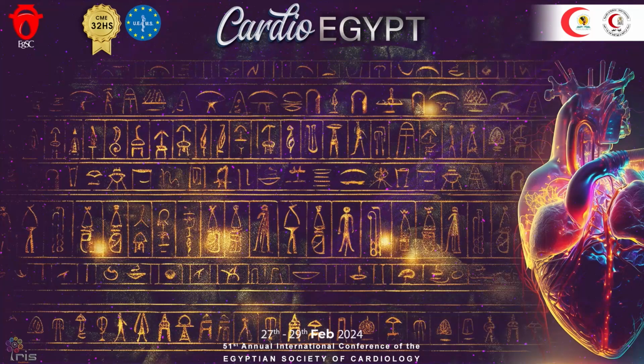Thank you very much, Haitham, for this very comprehensive and elegant talk. So, Ali, I think the future will be on left bundle pacing, not His bundle pacing. Yes, because His bundle pacing is technically challenging. It's more demanding, with dislodgement and very high thresholds, sensing problems, and the anatomical situation, where it is surrounded by structures that may cause oversensing.